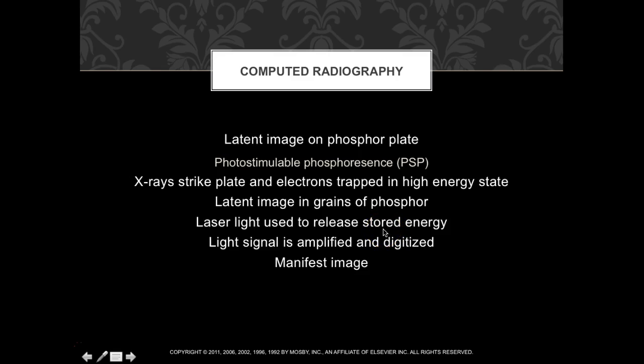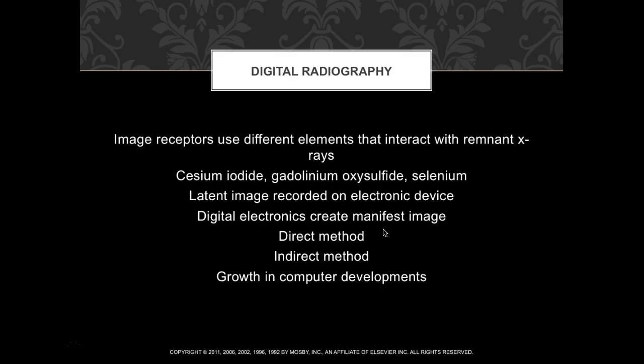With computed radiography, you have a latent image on a phosphor plate — photo-stimulable phosphorescence. X-rays strike the plate and electrons are trapped in a high-energy state. We use a laser light to scan the plate, releasing that stored high energy. The laser signal is amplified and digitized, giving us the manifested image.